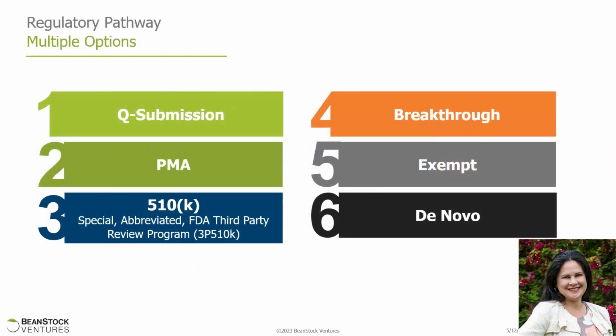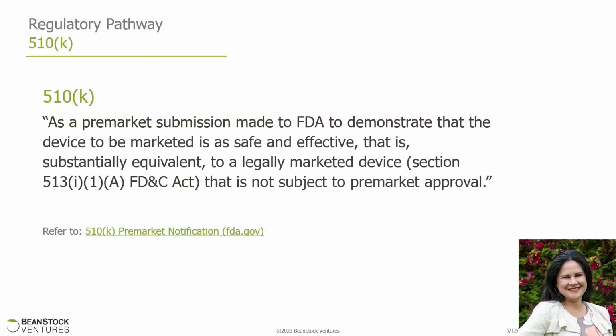In addition to your device classification, there's multiple regulatory pathways. The Q-Sub, which is a free submission process for the FDA to get some of your questions answered. There's the PMA, the 510K, which includes special 510K, abbreviated 510K, third-party review. There's also breakthrough designation, exempt, and de novo. I'm going to focus on the 510K.